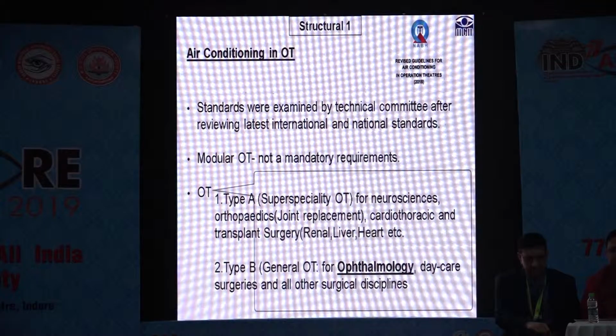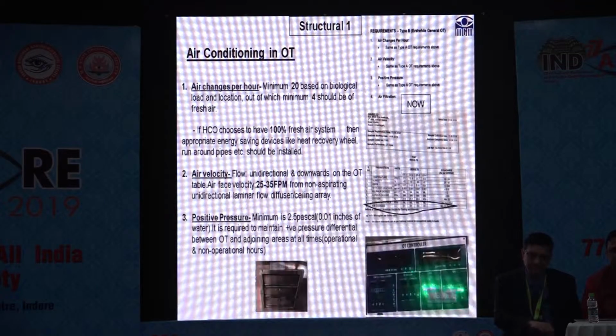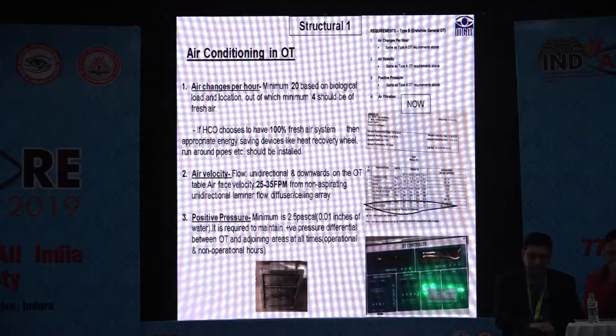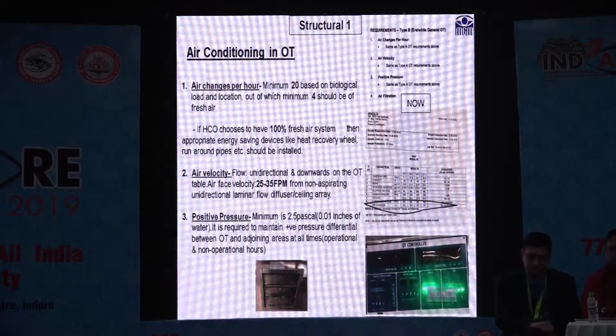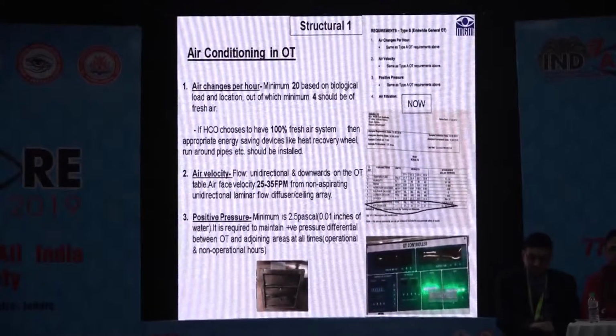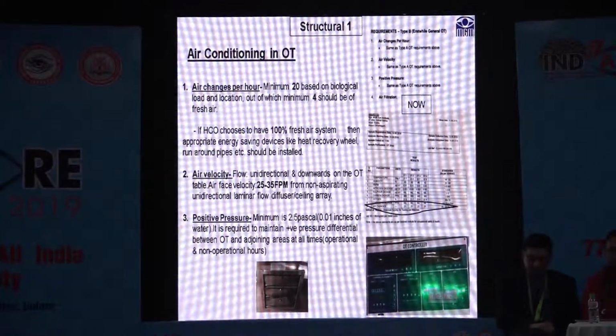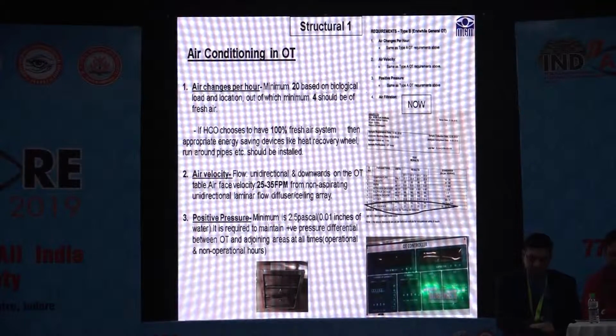Now, NABH has made stringent guidelines for air conditioning in the OT, which was already described. There should be a minimum of 20 air changes per hour, of which at least 4 should be fresh air. Air velocity is to be maintained at 25 to 35 feet per minute, which should be unidirectional and downwards, and a positive pressure of minimum 2.5 Pascal should be maintained at all times.